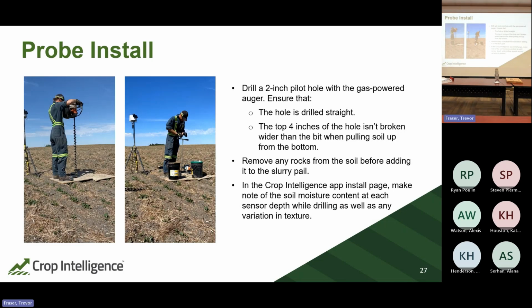So what you're going to do is drill a 2-inch pilot hole with the gas-powered auger. Actually, I'm going to step back a second. We always mark the probe length on our drill so that we know how deep we have to drill. I just use electrical tape. I measure the depth plus another 3 inches so that I'm deep enough with the probe install, because you don't want to drill most of the way and set the probe in and it is sticking out of the ground too far. So mark on your manual auger and on your gas powered auger bits the lengths that you need so that you know when you're going to hit that depth and you aren't drilling excessively or not drilling enough.